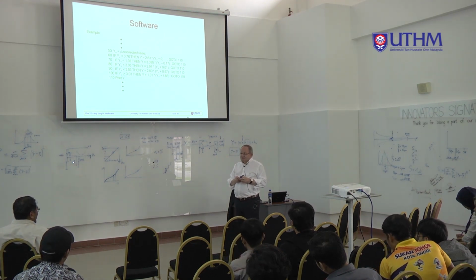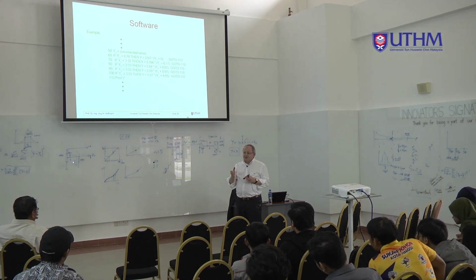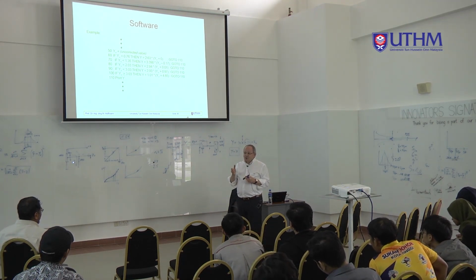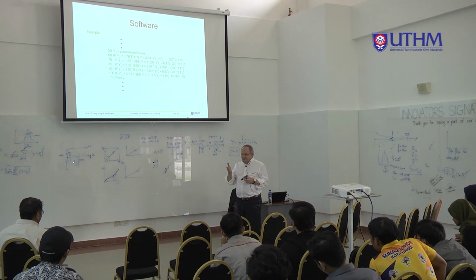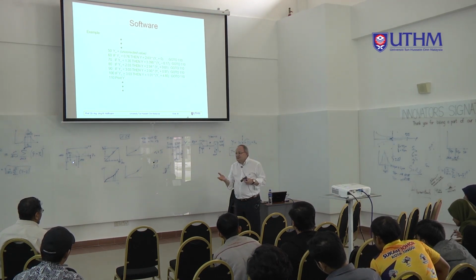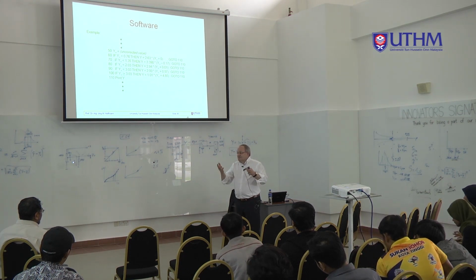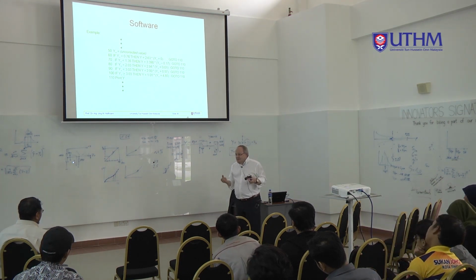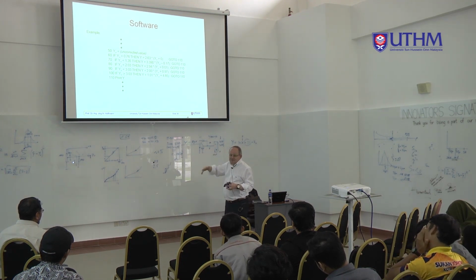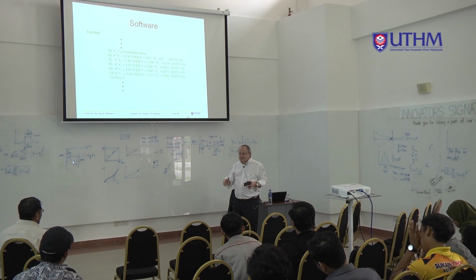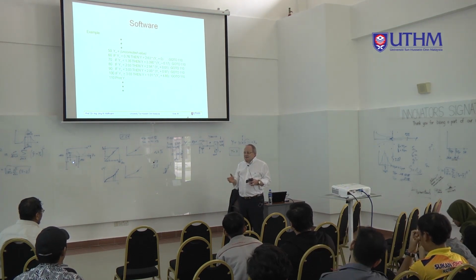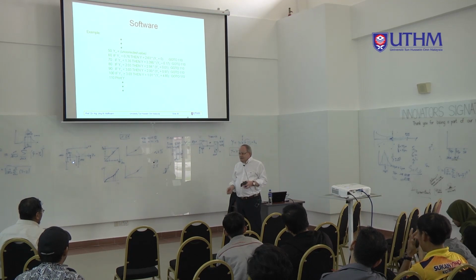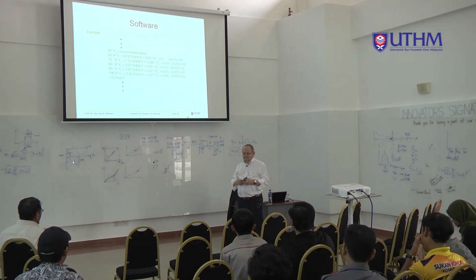Of course, you can only reduce it, especially when you have a measurement signal where you know it's very slow. For example, temperature will never change in the range of 100 hertz. You can be happy when it changes in 1 or 2 seconds - that's very fast for a temperature measurement. So that means everything above 1 hertz you can filter.